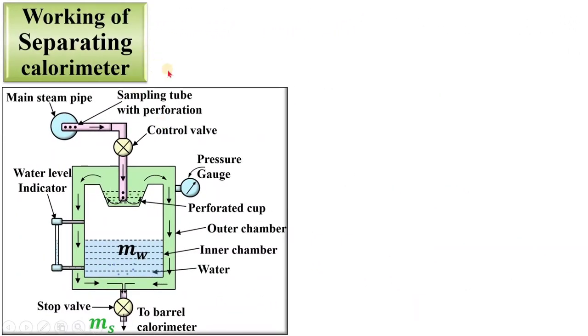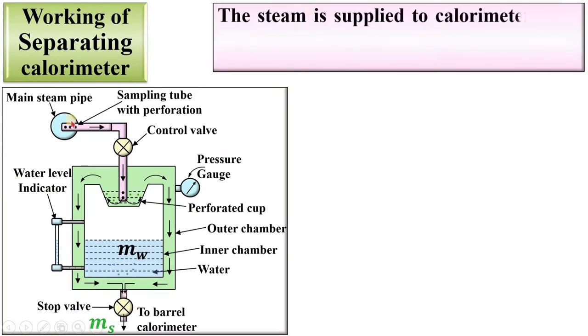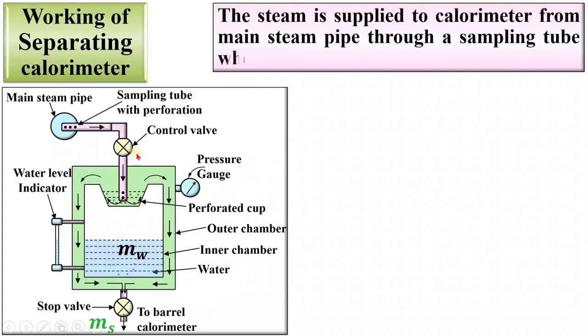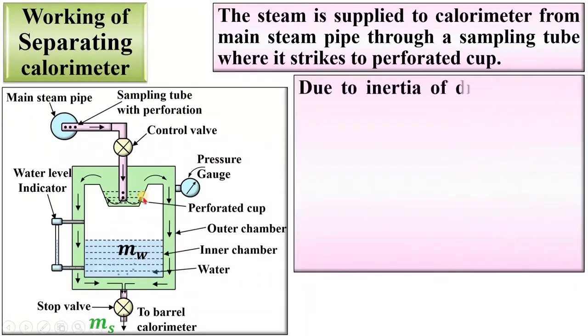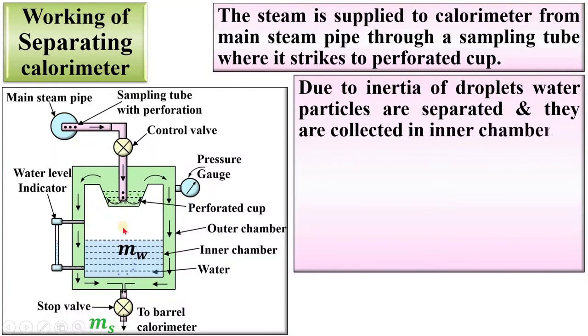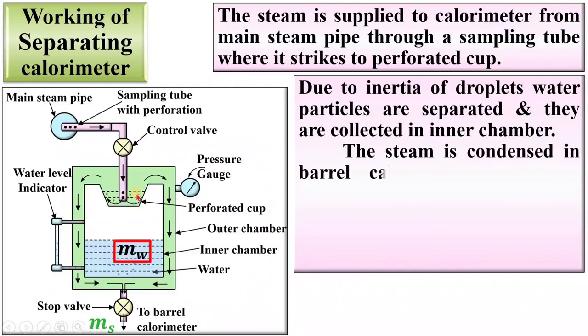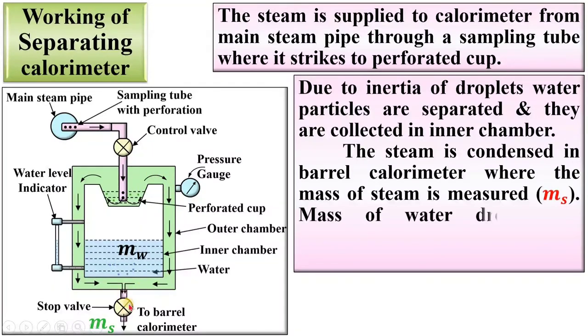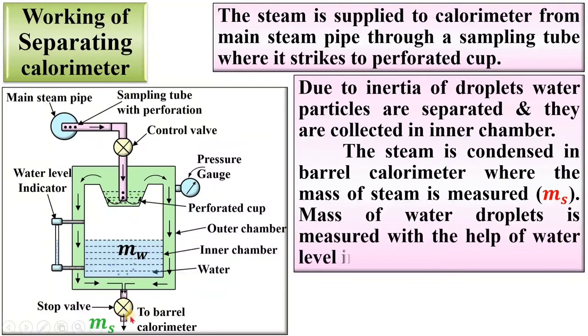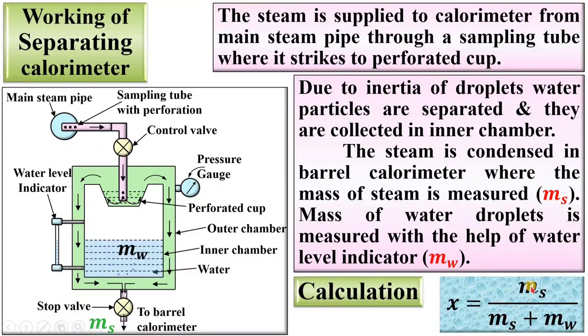Now let's see the working of the separating calorimeter. The steam is supplied to the calorimeter from the steam main pipe through a sampling tube, where it strikes the perforated cup. Due to the inertia of droplets, water particles are separated and collected in the inner chamber. The steam is condensed in the barrel calorimeter, where the mass of the steam is measured. If you are able to measure ms and mw, then you can find the dryness fraction of the steam using this formula.